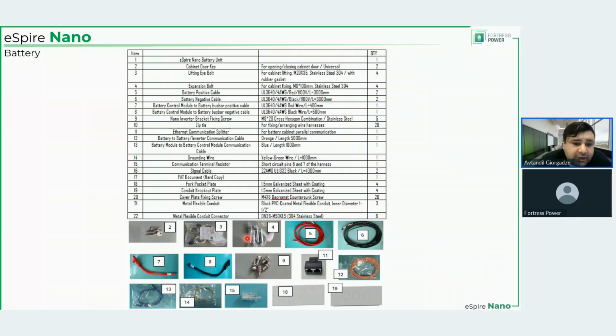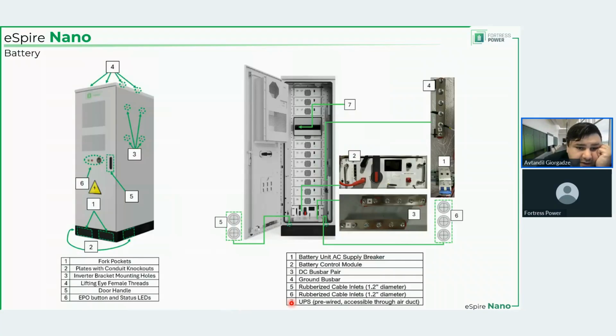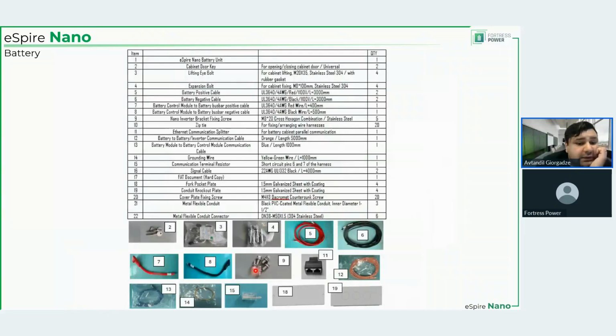5 and 6, those will be your positive and negative cables that will connect the DC bus bar to the inverter mounted on the side of the cabinet that contains those DC bus bars. Number 7 and number 8, these are DC cables that will connect the battery management unit, this one, to the DC bus bars. Number 9, obviously, the inverter bracket screws. You have those with the inverter as well, though, so maybe you're not going to use these after all, but nonetheless, they are there. Number 11, this is the Ethernet communication splitter.